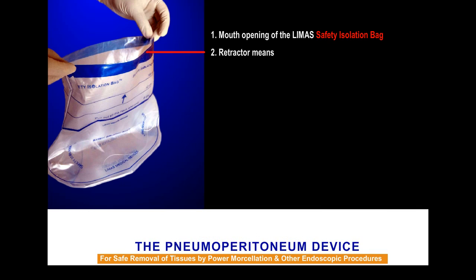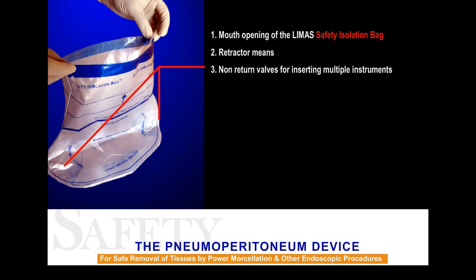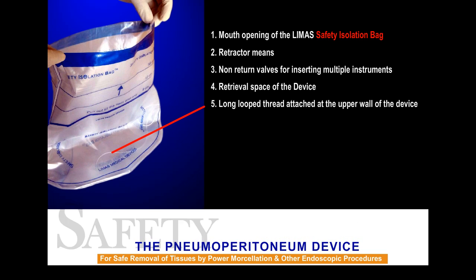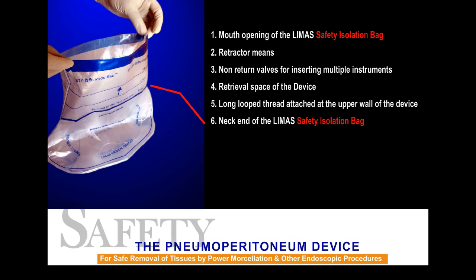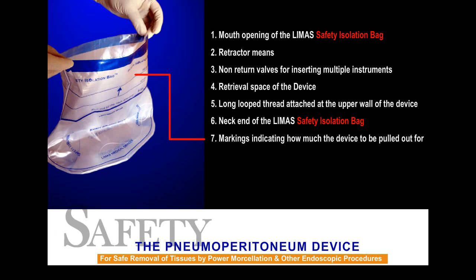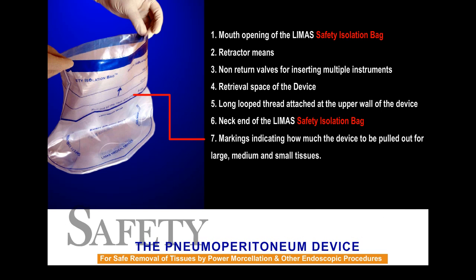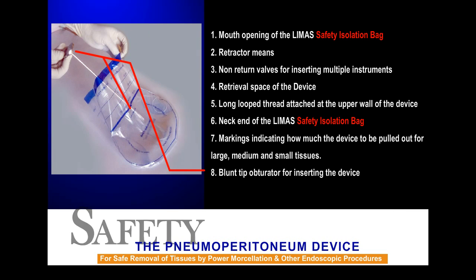Components of the LIMAS Safety Isolation Bag: 1. Mouth opening of the LIMAS Safety Isolation Bag. 2. Retractor means. 3. Non-return valves for inserting multiple instruments. 4. Retrieval space of the device. 5. Long looped thread attached at the upper wall of the device. 6. Neck end of the LIMAS Safety Isolation Bag. 7. Markings indicating how much the device is to be pulled out for large, medium, and small tissues. 8. Blunt tip obturator for inserting the device.